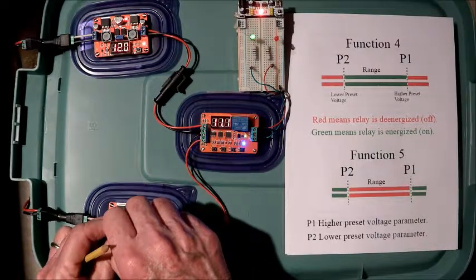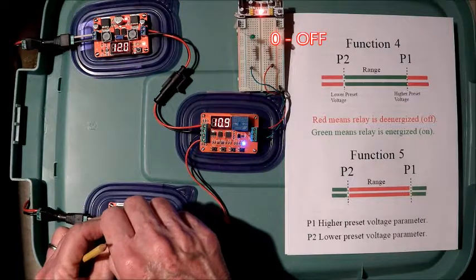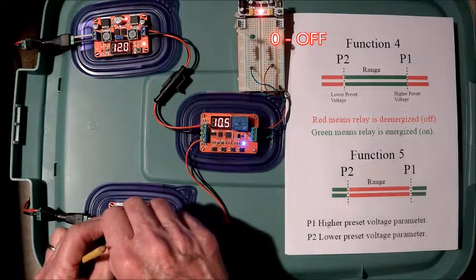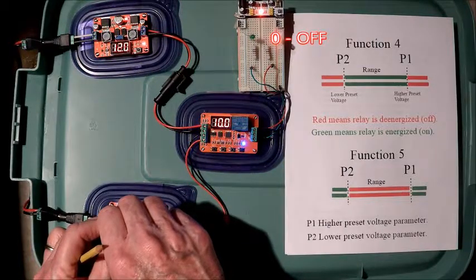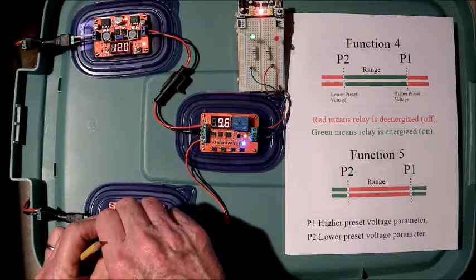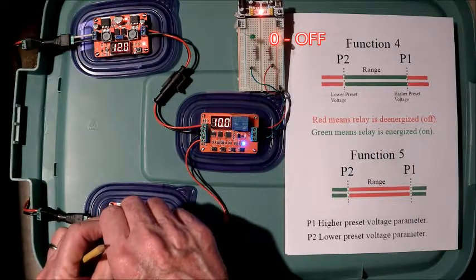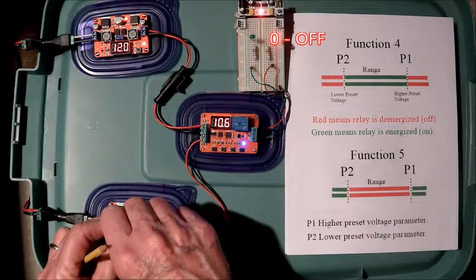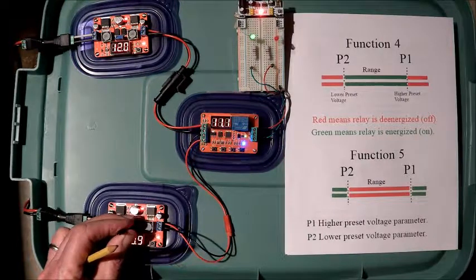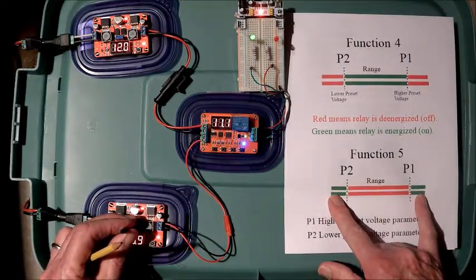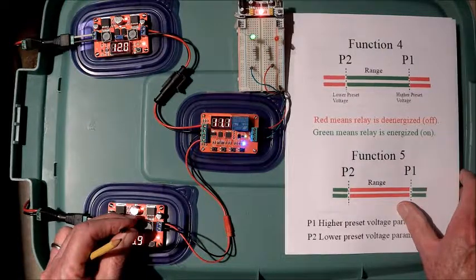Coming down below the high preset voltage, the relay should de-energize. It will stay de-energized until it goes beyond the lower preset voltage. When it comes back up above 10 volts, it will energize. It will stay energized until it passes 11 volts. Outside the range, the relay is on. Inside the range, the relay is off. Just the opposite of what you have with Function 4.